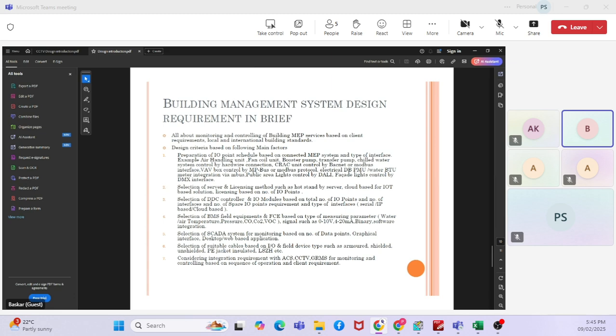When we talk about a CRAC unit, it can be integrated with BACnet or Modbus. It will not have any hardware input/output apart from only giving the command. So the client is looking for the complete parameters to be monitored. We have to look for the specification on the single line diagram.